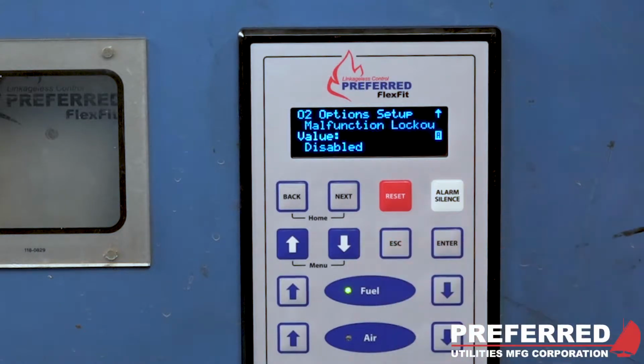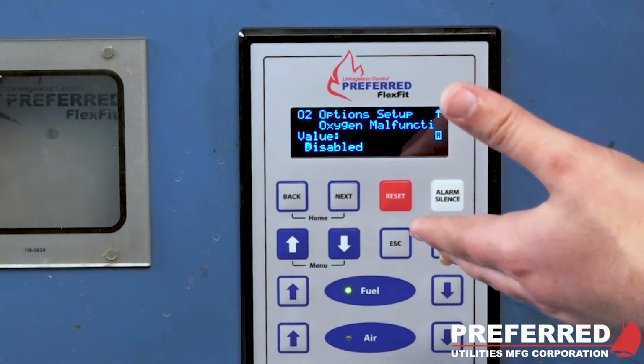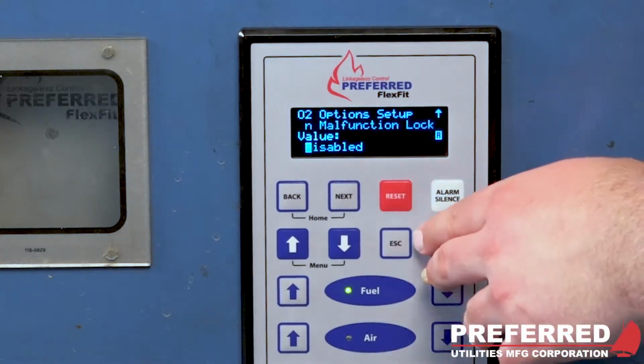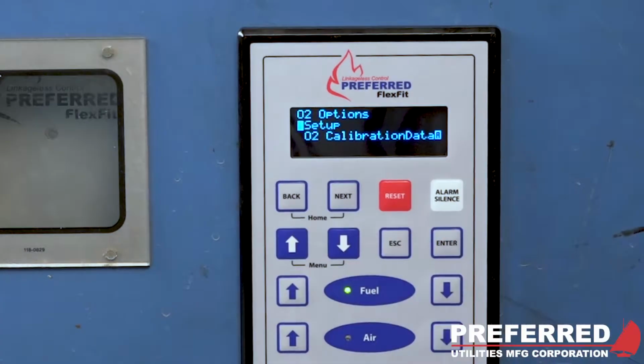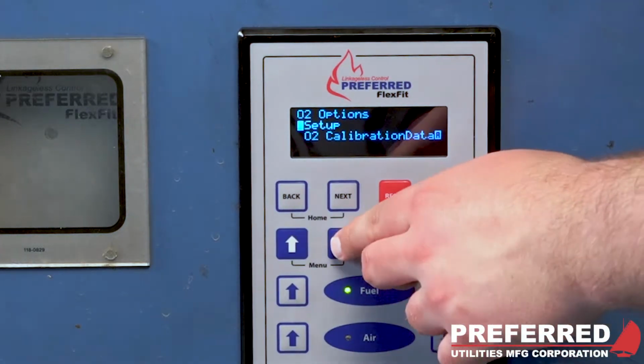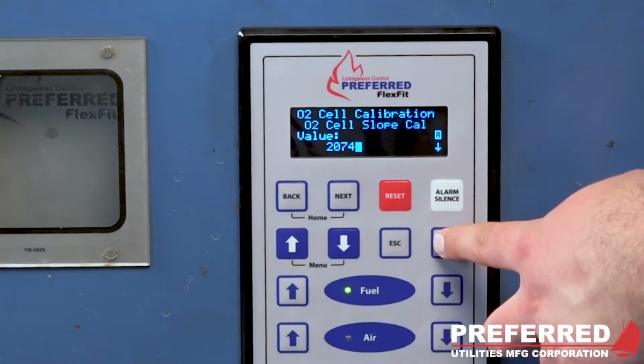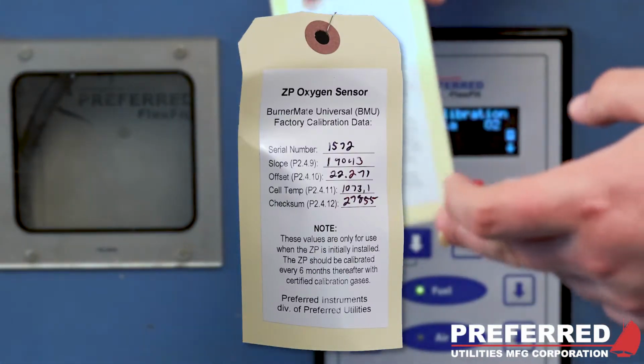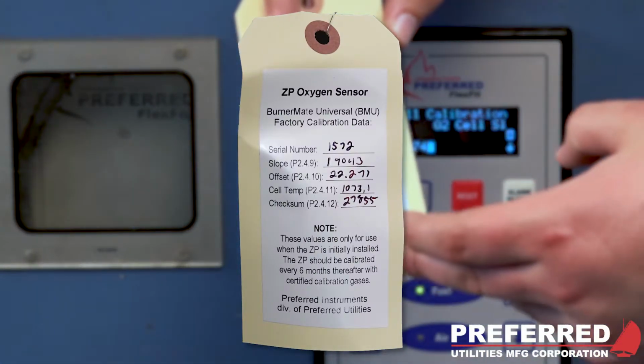Okay. And also there's self-diagnostics in the O2 sensor. So if any of those diagnostics give you an error, you can get an oxygen malfunction lockout. You can enable or disable that. The next menu option is O2 calibration data. We will enter that. And this calibration data will come from a tag that is shipped with your specific analyzer.